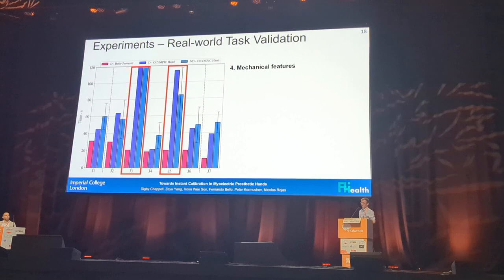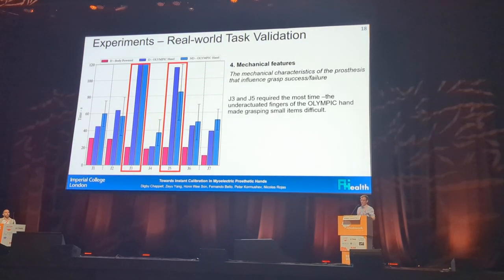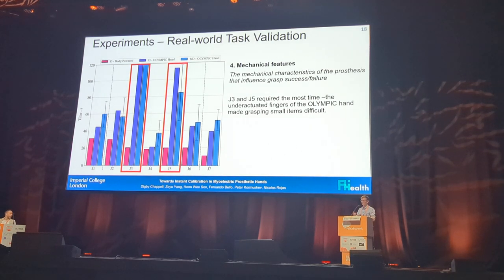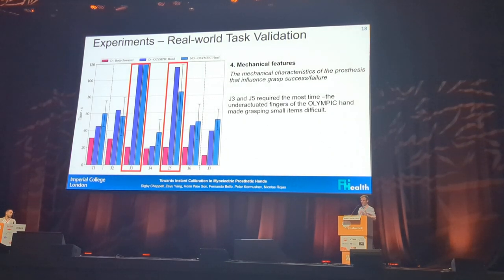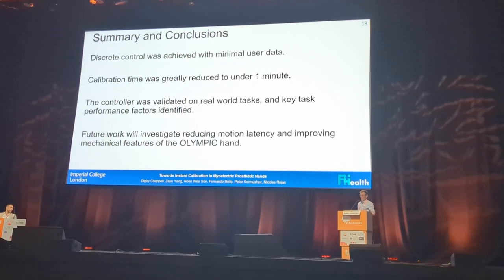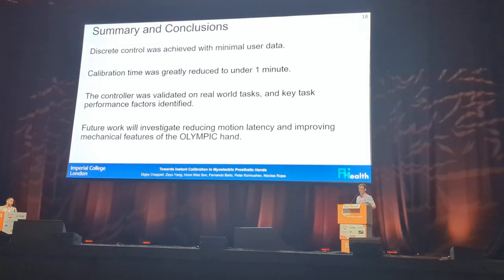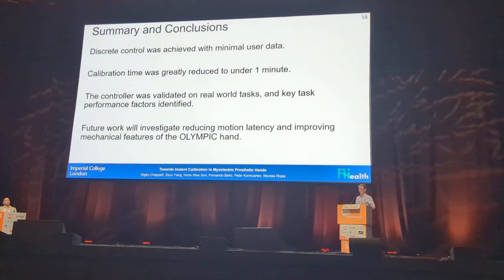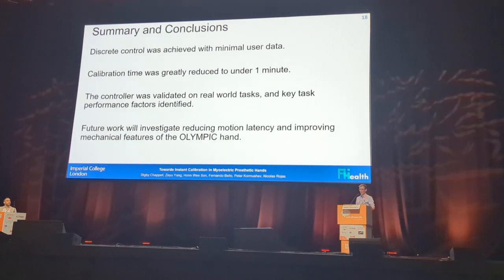Finally, the mechanical features of the Olympic hand have a big impact. The Olympic hand has underactuated fingers, which means that if you prematurely contact anything or mistime it, they won't close in the same way and you won't achieve the pinch grasp of small items. So in summary: discrete control was achieved with minimal user data and calibration under a minute. We validated it on real-world tasks and saw that body power is much better — but we identified key performance factors that will influence future work, mainly around reducing motion latency and improving mechanical features of the Olympic hand.